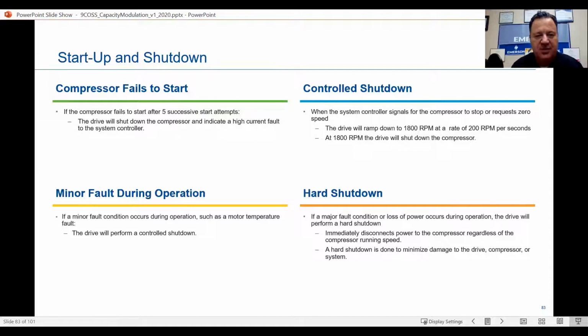If a minor fault condition occurs during operation, such as a motor temperature fault, the drive will perform a controlled shutdown. Hard shutdown is defined as follows. If a major fault condition or lost power occurs during the operation, the drive will perform a hard shutdown. It immediately disconnects power to the compressor regardless of the compressor running speed. A hard shutdown is done by minimizing the damage to the drive and compressor or the system.